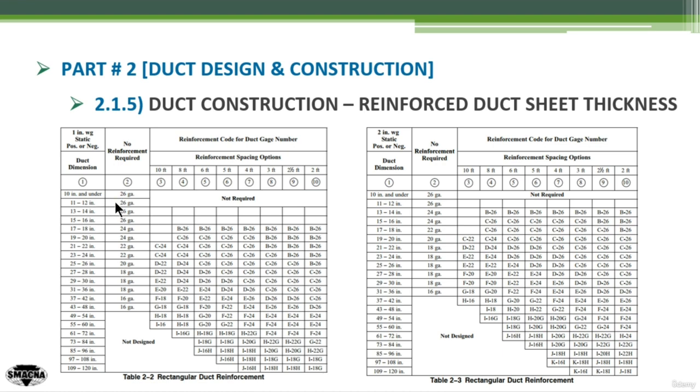I can use 24 gauge sheet metal thickness for the 20 inch. For the 12 inch, I can use 26 gauge if required. There is no reinforcement required in this case.